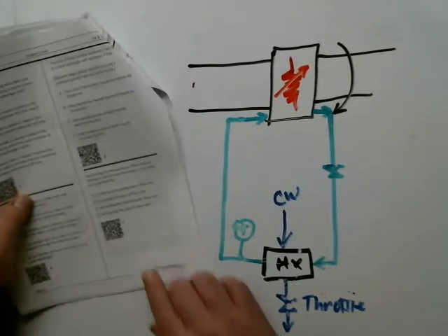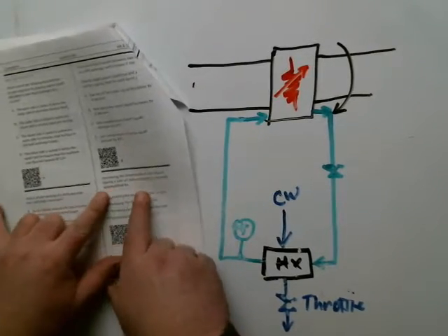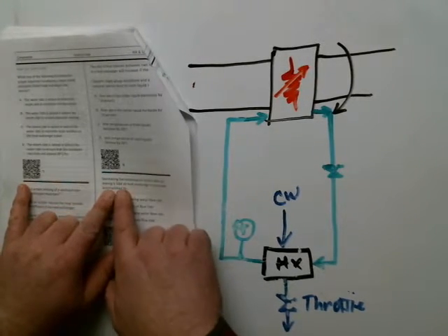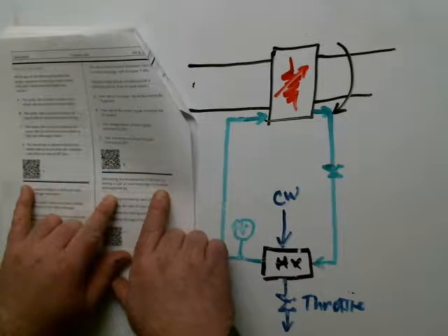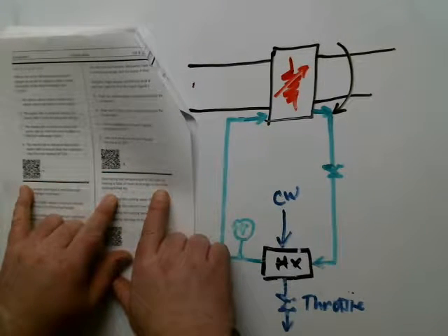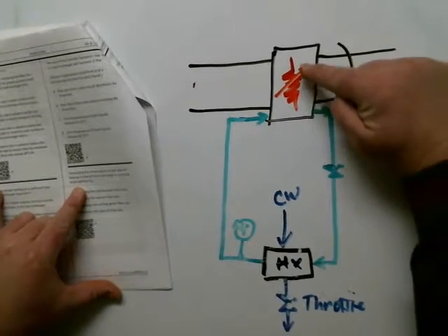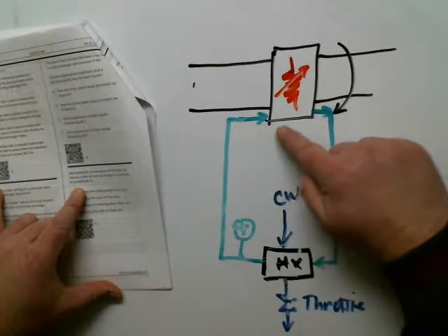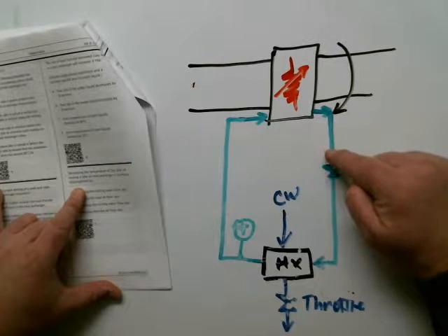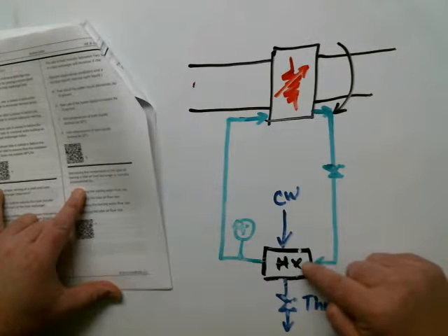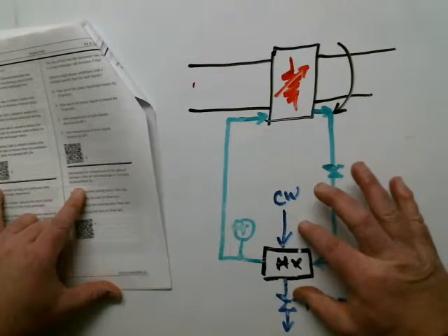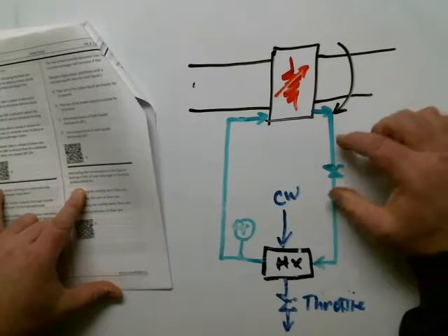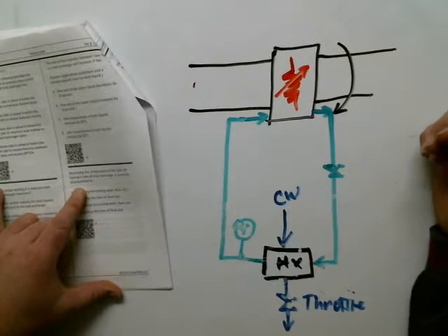All right, we're on this last question here, and this is typical of the exam bank questions. Decreasing the temperature of the lube oil leaving the lube oil heat exchanger is normally accomplished by. So what I've done here is I've given you a bearing with a variable heat load, and here's the shaft, and here's oil entering that bearing, lubricating and cooling it, and hot oil leaves, and here's a throttleable valve, and it comes on down to a heat exchanger that has cooling water flowing through it, and so it cools the oil. Now here's cooler oil going back to the bearing. Obviously I would need some pumps and such in here, but I've omitted them for now.